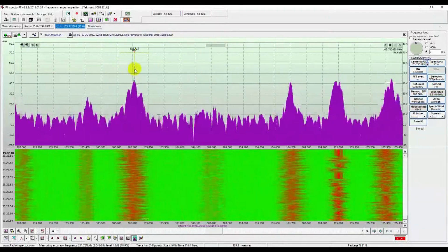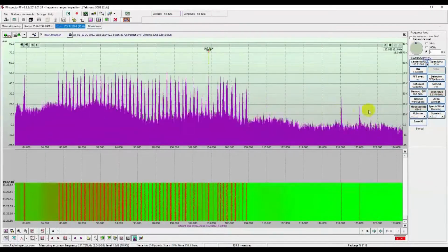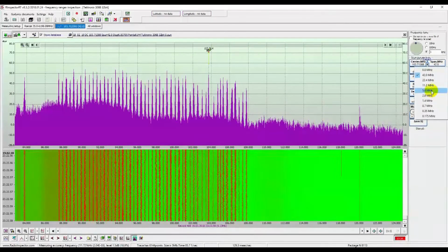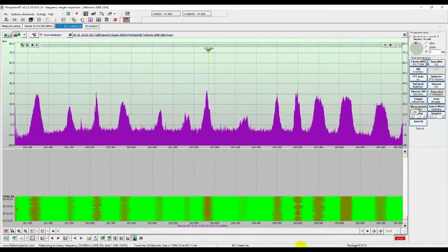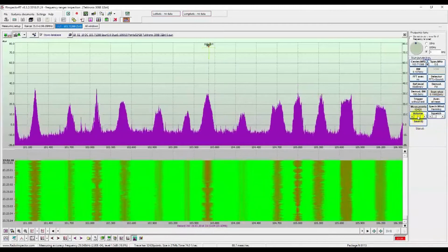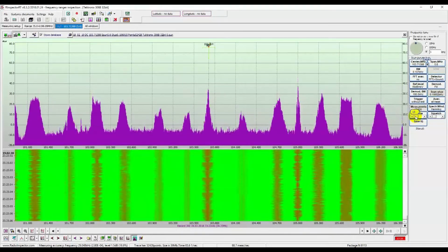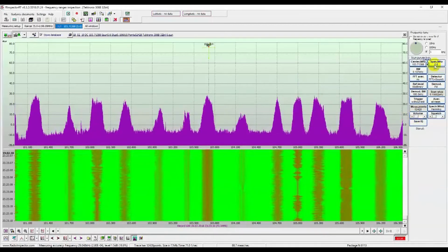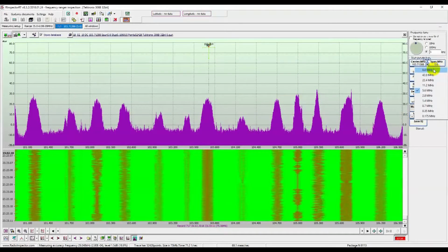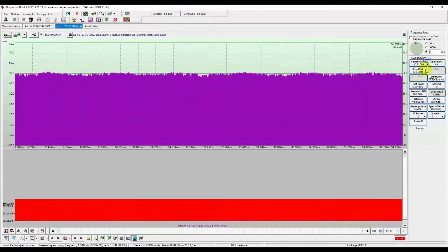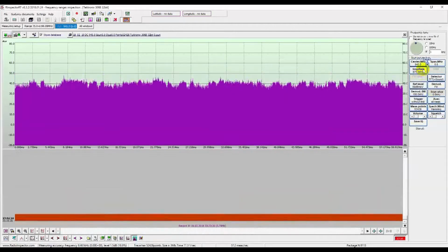In addition to standard options in RF signal analysis mode, Tektronix 306B provides demodulation of selected signal with simultaneous spectrum monitoring. The instrument also supports zero-span mode, what is clearly observed on GSM signals. Here we can see the time slots of GSM signals.